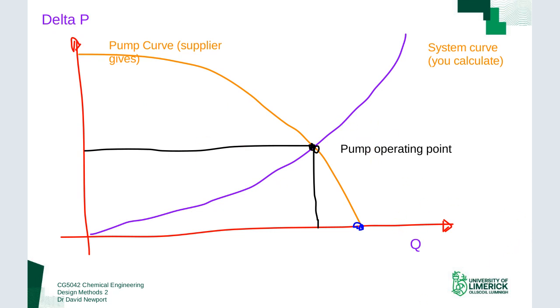The key thing I want to get across in this lecture is that this pump system curve is your focus for all your design changes. Everything we do, we look at how we can change the pump curve — things like changing the speed of the pump, putting pumps in series or in parallel, and things we can do with the system, like reducing or increasing the system curve — to figure out what the operating point is.